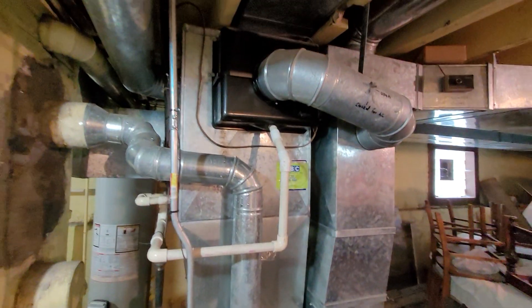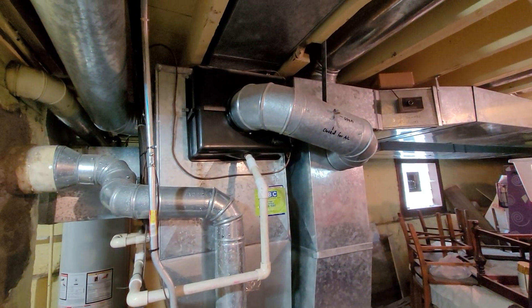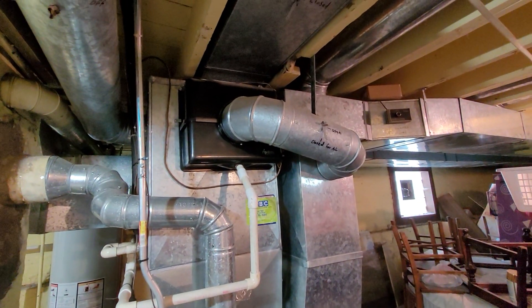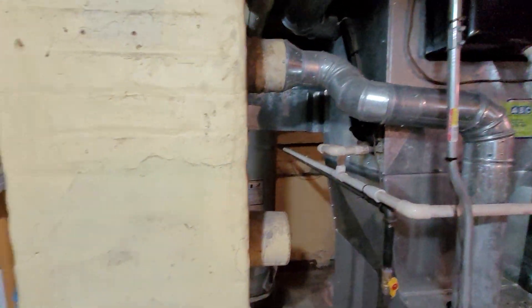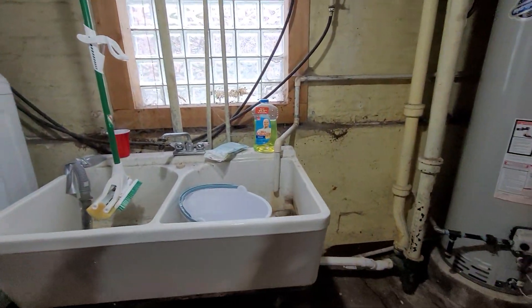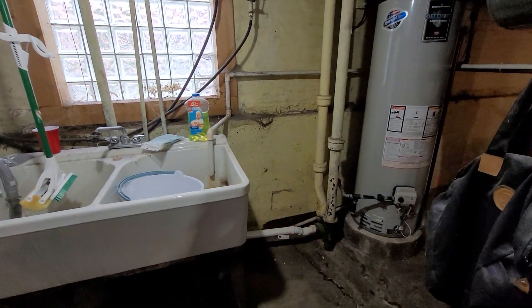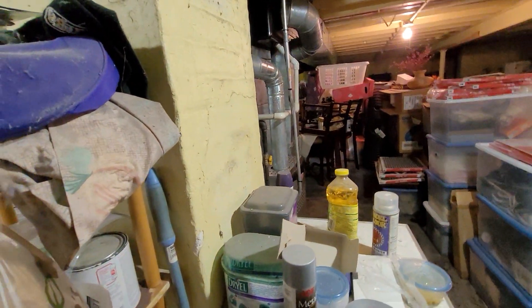The humidifier is circa 1992-94. We will likely be putting that in at the same time. The AC drain line for both of these comes around and heads toward the laundry sink. However, the height of this sink versus the height of the top of the furnace where the coil drain is going to be is too low.